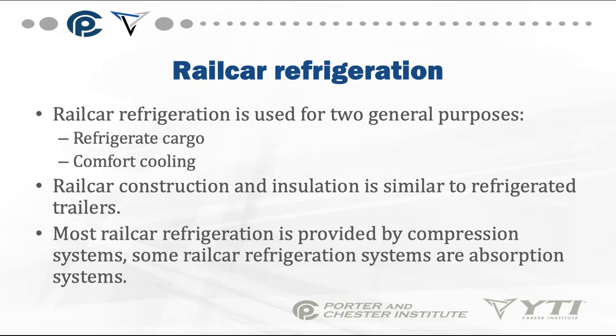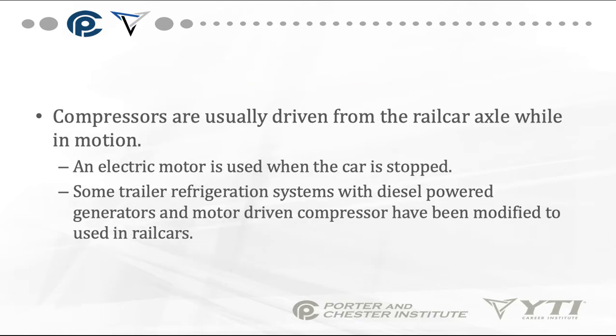Rail car construction and insulation is similar to refrigerated trailers. Most rail car refrigeration is provided by compression systems, though some use absorption systems. Compressors are usually driven from the rail car axle while in motion, and an electric motor is used when the car is stopped.